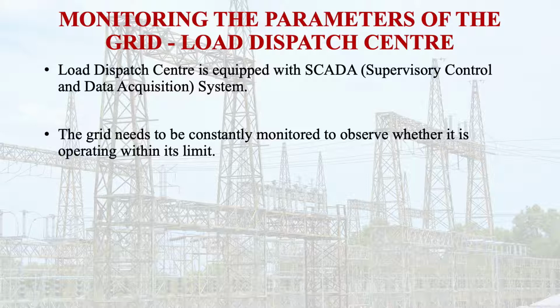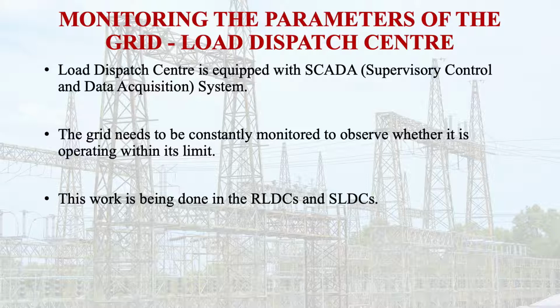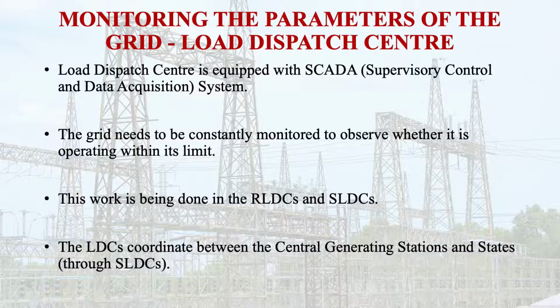All the instructions of the grid operator have to be followed. It is essential. All instructions are also recorded on a sound recorder to be replayed at the time of the analysis of a grid incident or any contingency. The grid needs to be constantly monitored to observe whether it is operating within its limits. This work is done by the RLDC, Regional Load Dispatch Center, and the SLDCs, State Load Dispatch Centers. These load dispatch centers coordinate between the central generating stations and the states through the SLDCs.